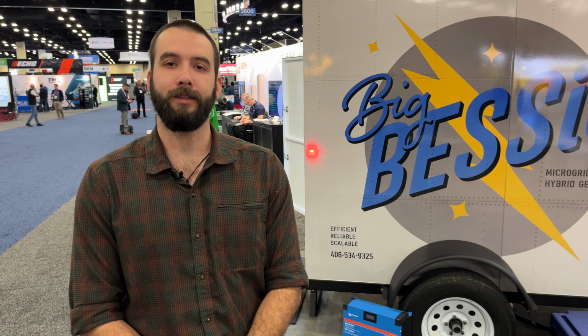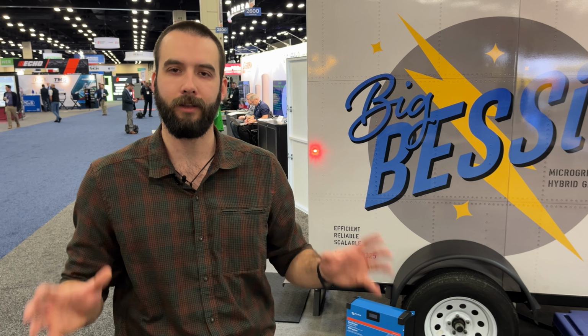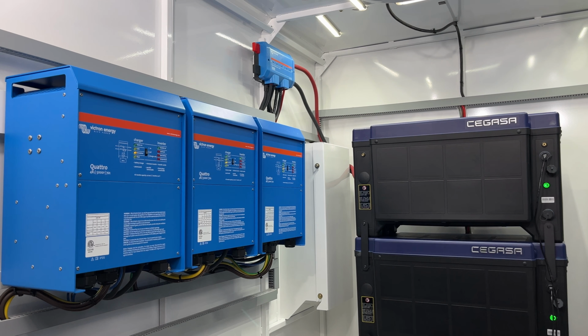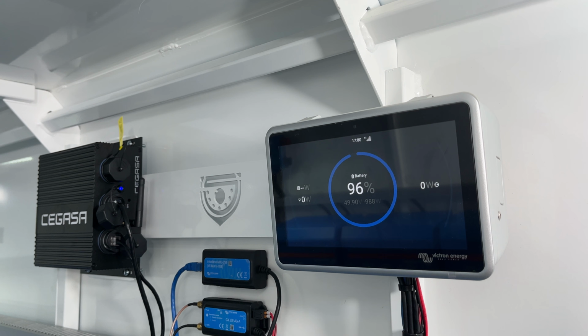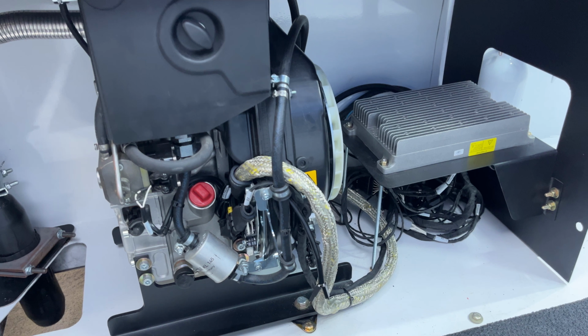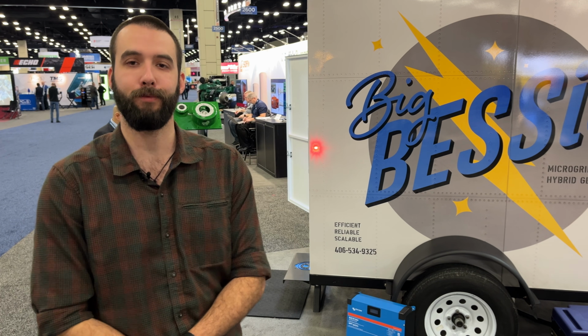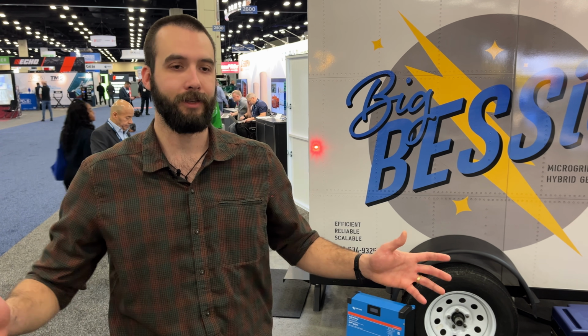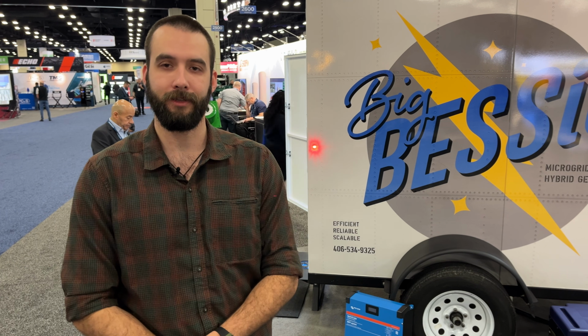The idea behind the Big BESSie is to handle those peaks and the valleys with perfectly clean inverter power out of the Victron Energy Quattro units that are the onboard power supply component of this hybrid generator trailer. All of that then comes from the Cegasa batteries, which store the excess energy generated by the Hatz. And from there, our duty cycle looks something like Hatz runs for a couple of hours, charges up the batteries. The inverters handle our peaks and our valleys of our load, and then once the batteries hit a predetermined state of charge threshold, Hatz kicks back on again, charges everything back up, and the cycle continues.